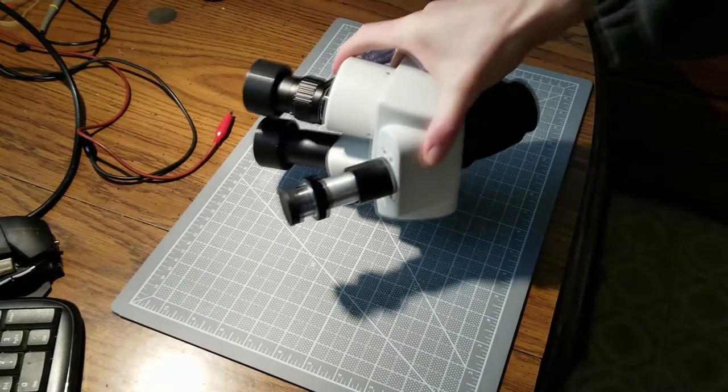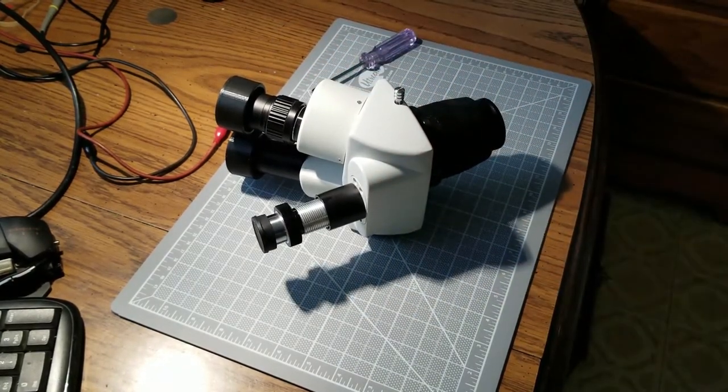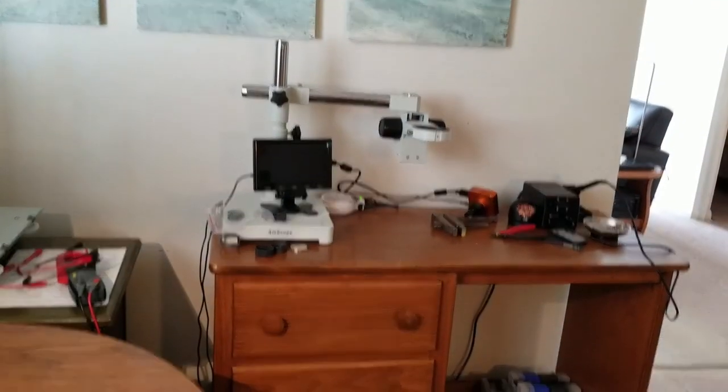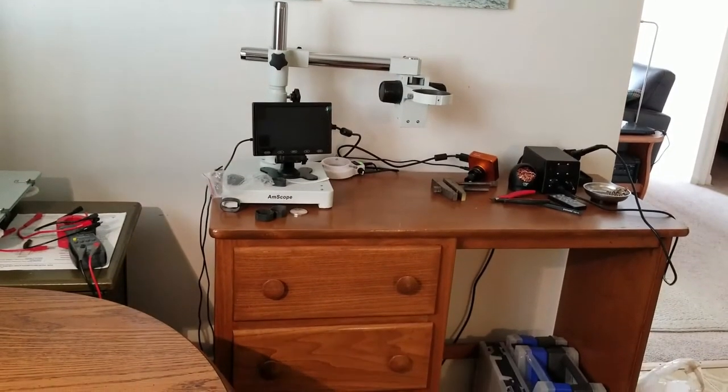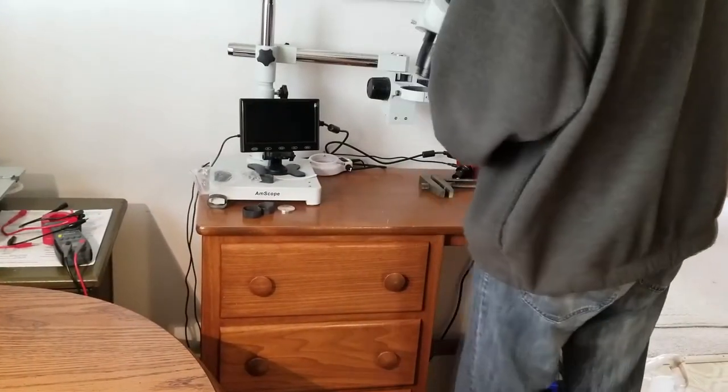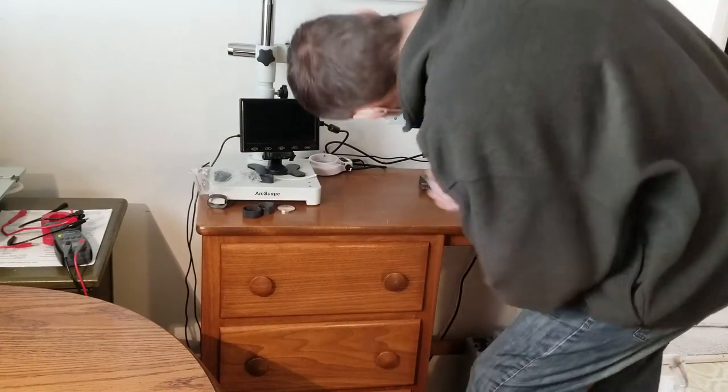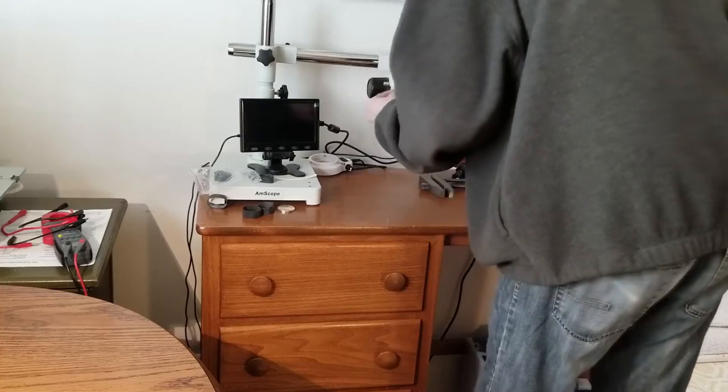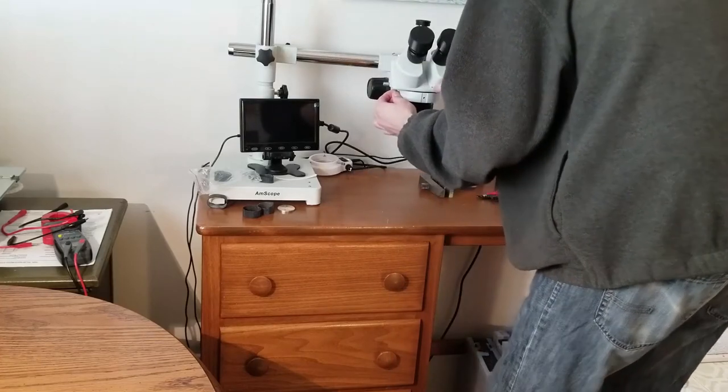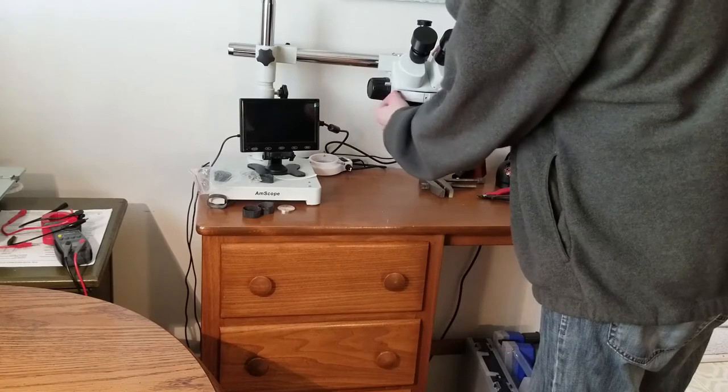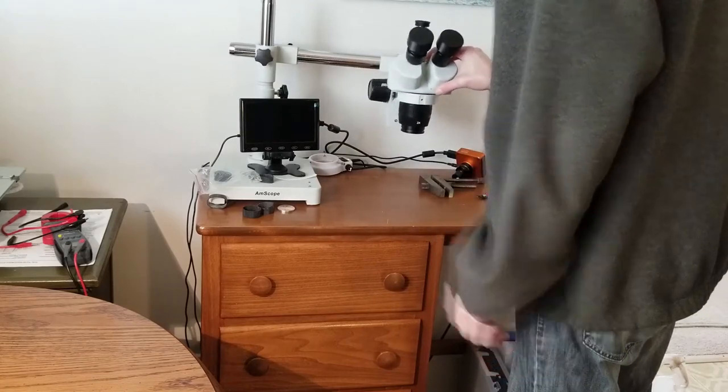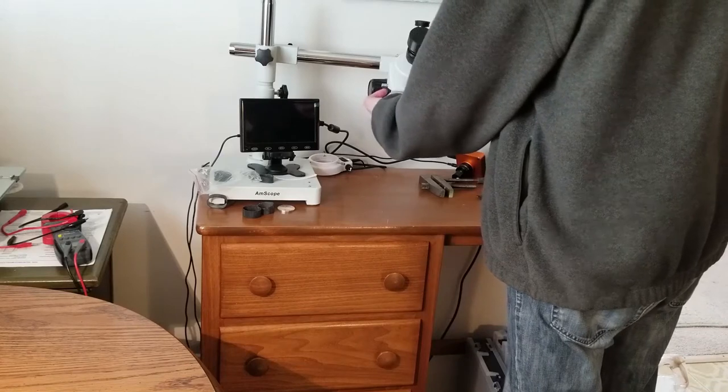Well, thanks for watching and hopefully this helped you in some way. If you're thinking about opening one of these and you're worried about getting dust or contamination on the lenses and you'd like to remove what you believe to be a shutter, it is not a shutter. It is a binocular microscope and you're just moving a beam redirector in and out of the way for the trinocular portion.